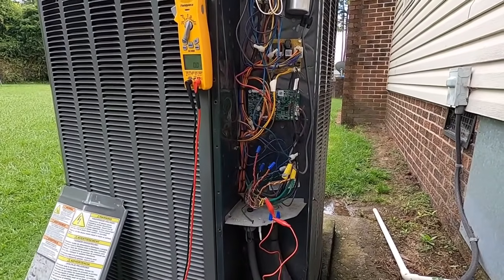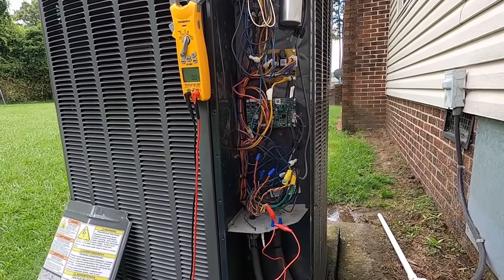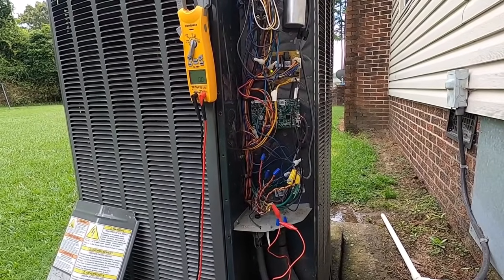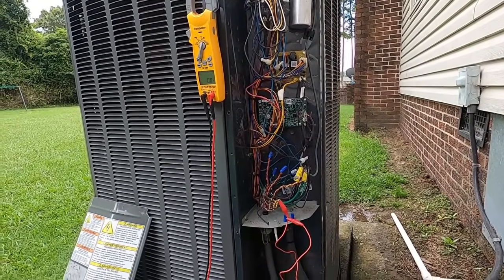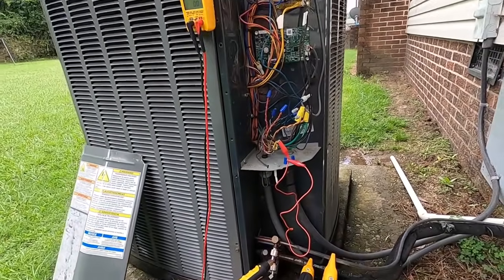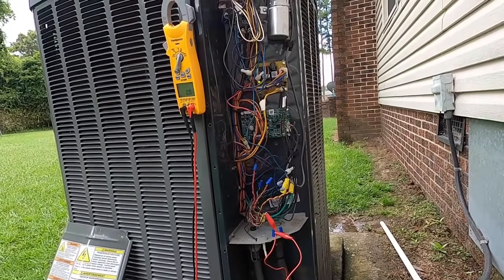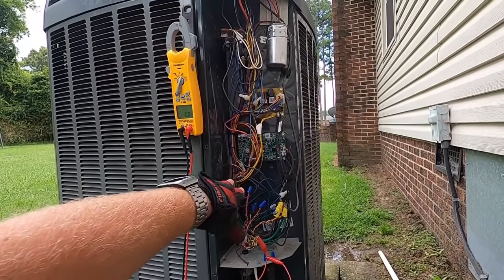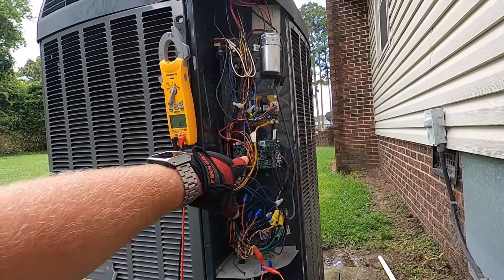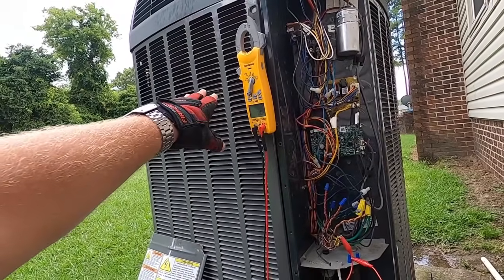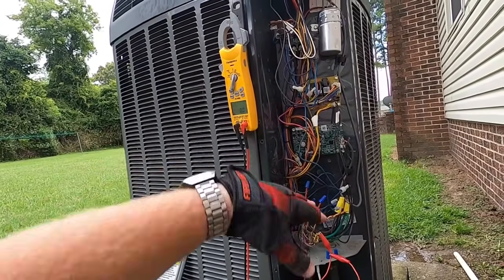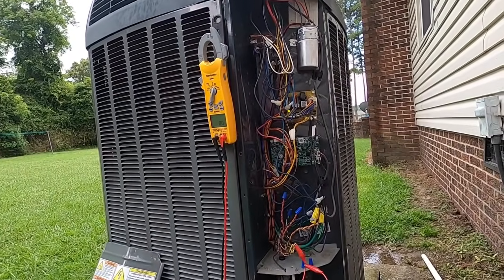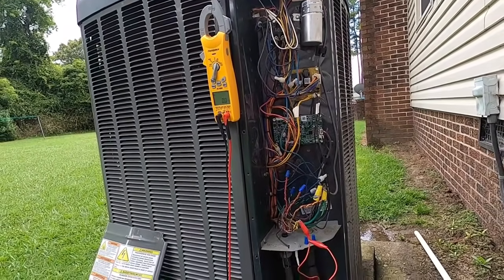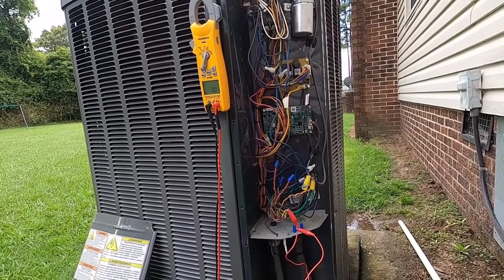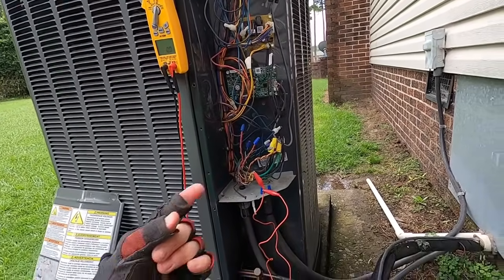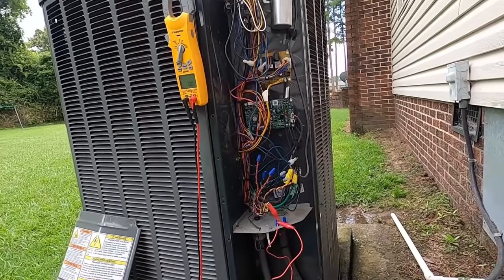But the EEV board, I've seen this in heat mode on these units twice. The first time somebody condemned a compressor that was bad in second stage, and then came out, put a compressor in it, and it didn't fix the problem. It turned out that when the EEV board was getting a call for second stage, it was just throwing the EEV out of whack and shutting it down, and then the compressor was going out. Put an EEV board in and it fixed it, and that may be the same problem here, with the exception that the EEV board inside is probably the problem. I'm just here to double check it.